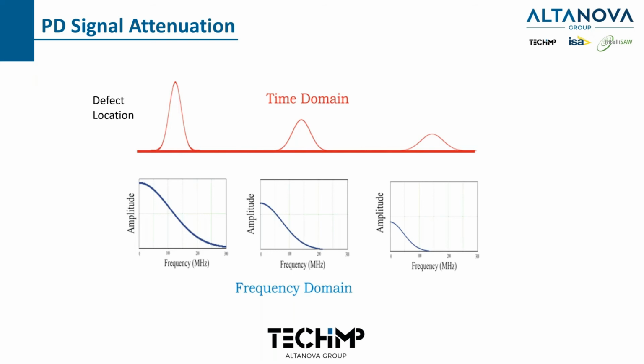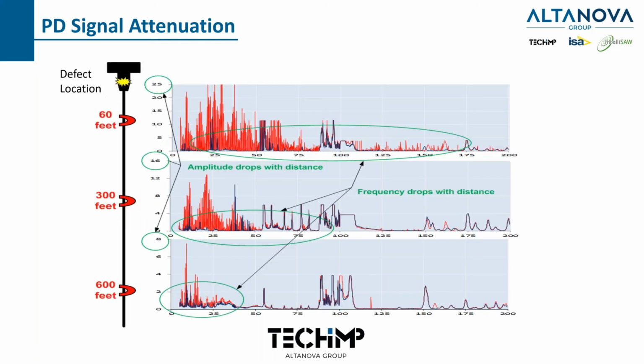Why is that important? Well, it helps us identify the location. Let's say we come in and we have a T-body with a partial discharge happening. That's where the little yellow dot is. And we take a reading 60 feet away. This is what we would see: 25 millivolts of amplitude, and a frequency range of about 15 to 175 megahertz. And then we move that sensor away and take a reading.